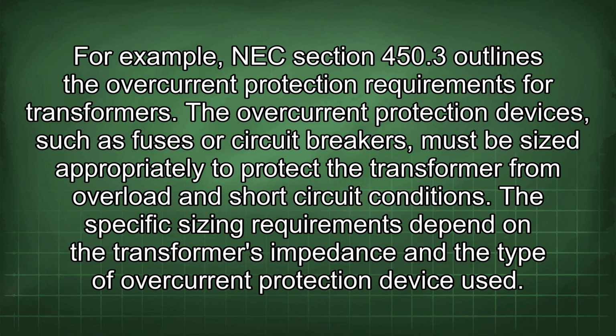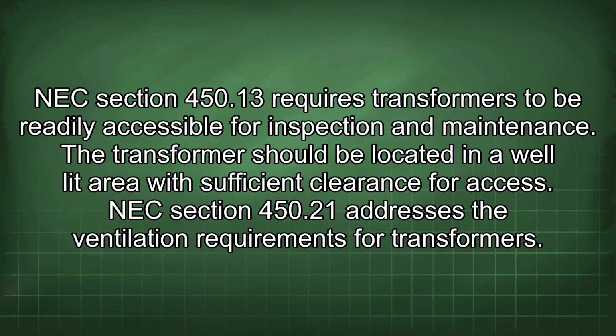For example, NEC Section 450.3 outlines the overcurrent protection requirements for transformers. The overcurrent protection devices, such as fuses or circuit breakers, must be sized appropriately to protect the transformer from overload and short-circuit conditions. The specific sizing requirements depend on the transformer's impedance and the type of overcurrent protection device used. NEC Section 450.13 requires transformers to be readily accessible for inspection and maintenance. The transformer should be located in a well-lit area with sufficient clearance for access.